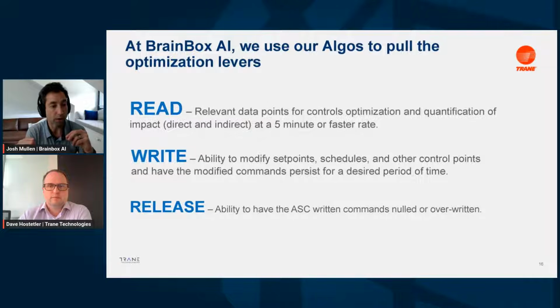And then they need to be able to write to set points and schedules and other control points. And what's really important is that command needs to persist. So it either needs to leverage the BACnet priority array, so that command has override ability and is taken into account and the system follows it, or some other means of overriding. It could be a timed override at a high level priority. But what's most important is when you write to a set point, that set point actually is the set point that is inducing that equipment behavior. So if you're trying to write to the static pressure set point, that fan should modulate to meet that static pressure set point, and it shouldn't actually be referencing another static pressure set point in the background, right?